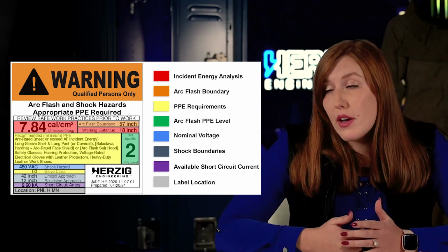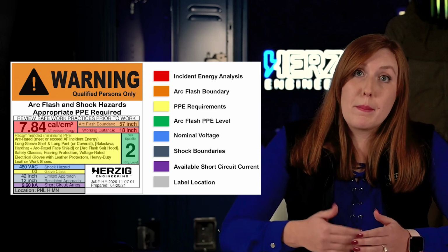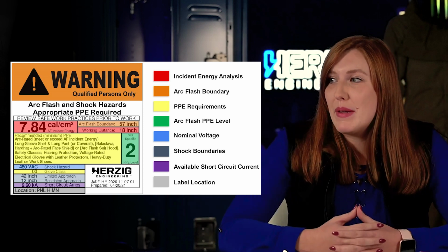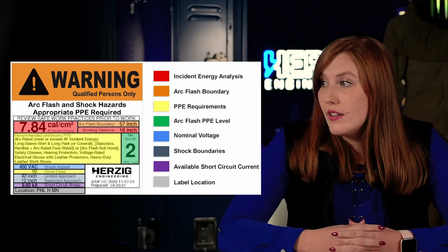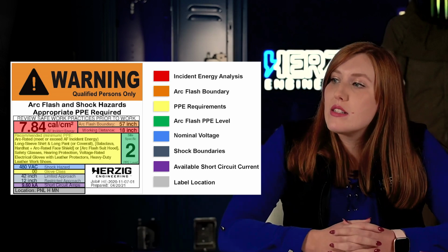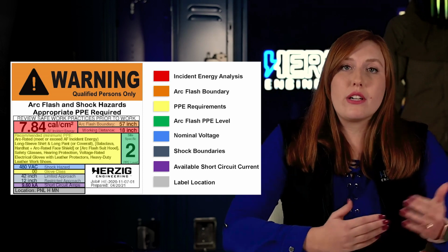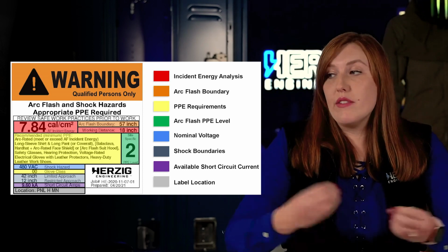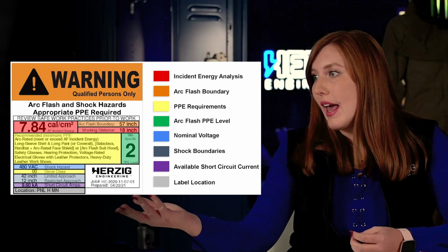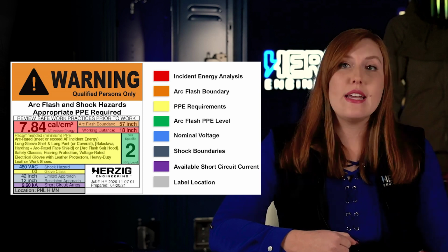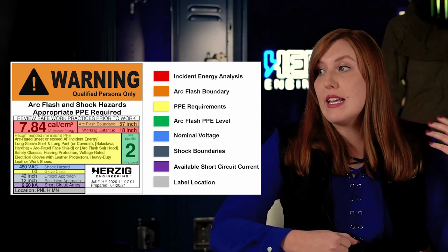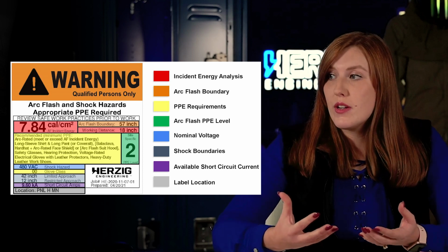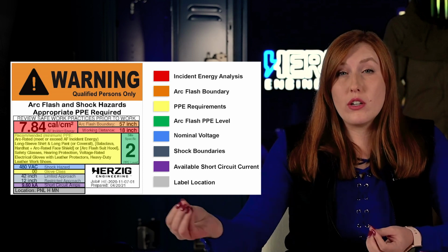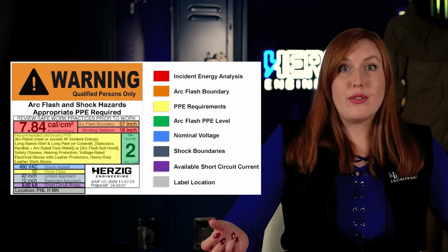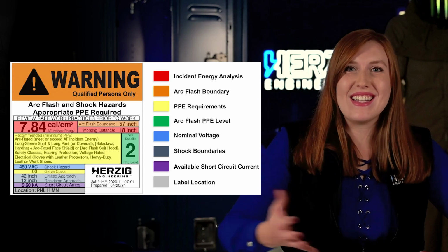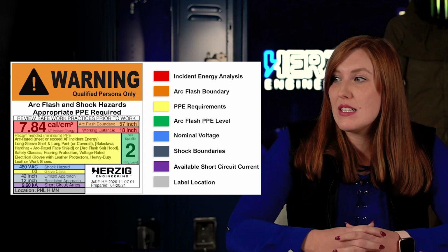Sometimes that arc flash boundary is lower though. And so 42 inches is the bare minimum. You don't ever want to set up your boundaries less than that because you don't want people exposed to the shock hazard either. The available short circuit current is another important piece of information. Oftentimes you can look at your enclosures or your breakers and make sure that, if there's a fault, 9.6 kA of available short circuit current is going to pass through it. Is that equipment rated for it or not? Because even if it doesn't instigate an arc flash, if there's enough current passing through because of a fault, but it's not rated for it, then that piece of equipment could actually blow up because of that. It's a whole different issue, but still an important piece of information.